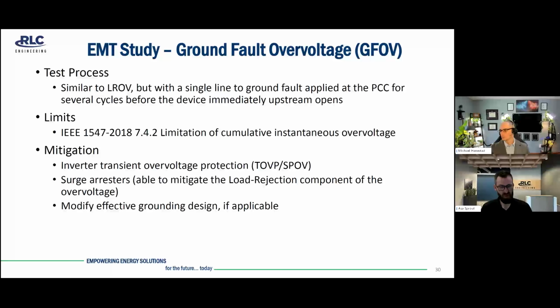But one additional tool we have is modifying the effective grounding design. And that's been shown to help. So effectively what you would do is reduce your zero sequence impedance path to ground. And again, that's been shown to mitigate GFOV in many scenarios we've encountered.